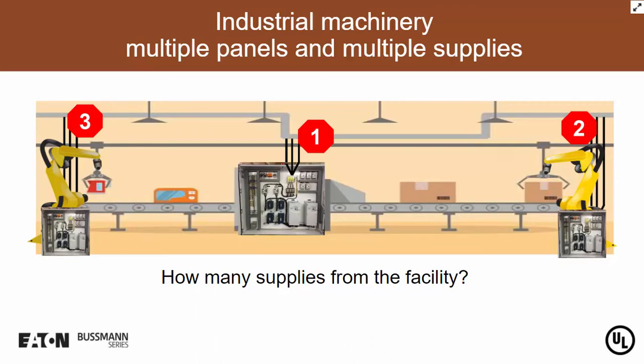So first, we want to make sure that we identify all the supplies from the facility. Many machines certainly could have more than one supply. You could have a supply for the power circuit, and then you could have a separate supply for the control circuit. Or you may have a machine that needs different voltages for different power circuits. So you could have multiple supplies for the power circuits and a separate source for the control circuit. So the machine could have different supplies. The requirement for displaying the short circuit current rating is such that you need to identify the rating for each supply. With the exception of one for control circuits, there is no requirement to identify the short circuit current rating for a supply for the control circuit. For the power circuits, multiple supplies, each supply would need to be identified with its short circuit current rating.